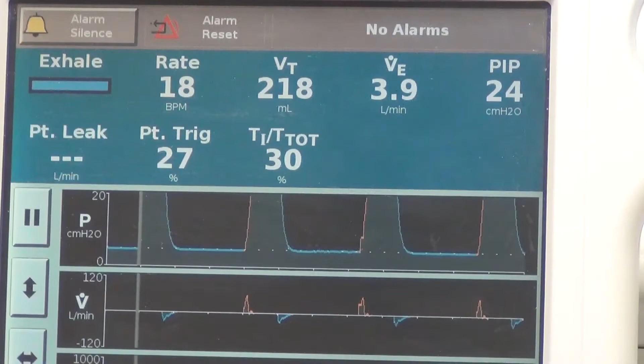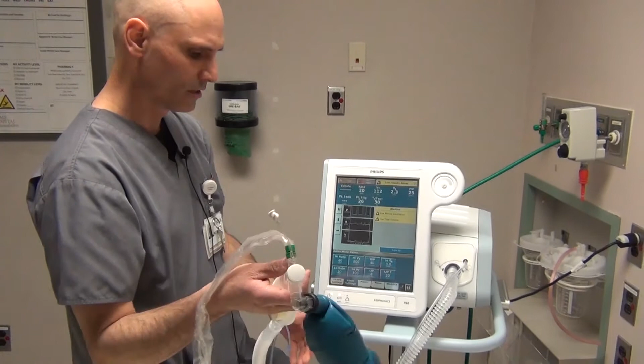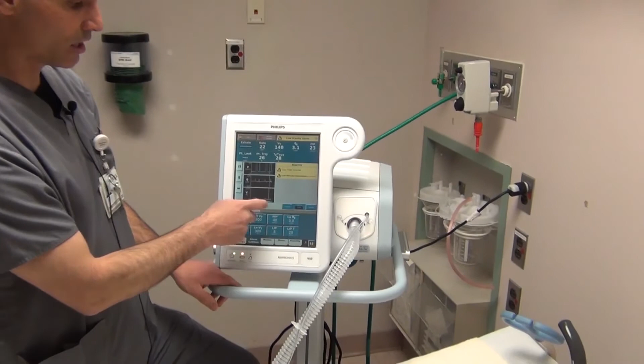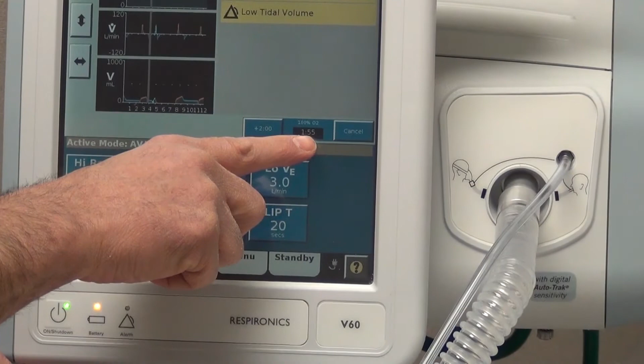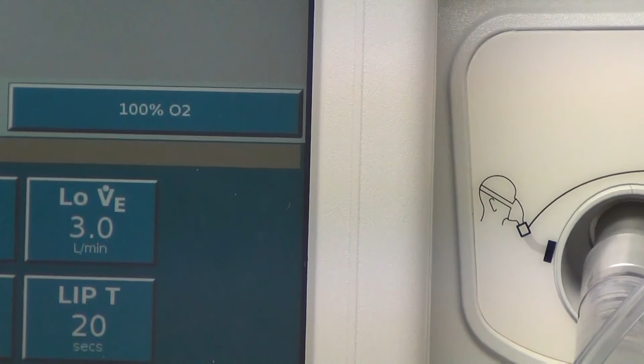And to reset the alarms, you hit there. And that basically concludes setting up this machine. If anytime you need to silence the alarm, you can hit the 2-minute, and that gives it a 2-minute quiet time. Let's say you wanted to disconnect the patient to reposition the tubing, which sometimes occurs as we're trying to reposition the patient. You can keep it quiet. Anytime you want to suction a patient, you can hit the 100% oxygen, and it'll give 100% oxygen. If you notice, it's for 2 minutes and it has a countdown. And if you change your mind, you can always hit cancel and it brings it back to whatever your setting is in the machine.